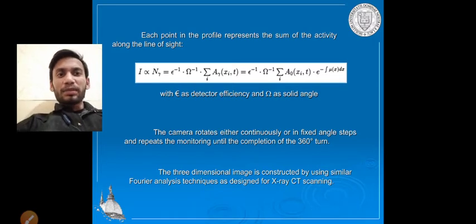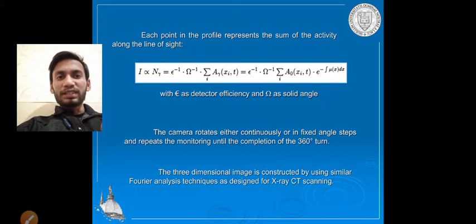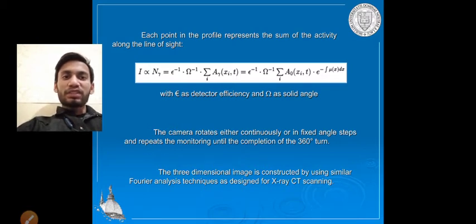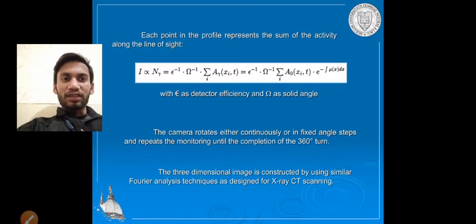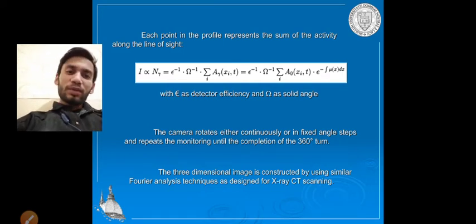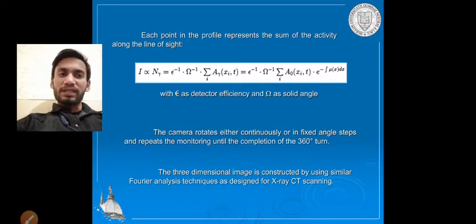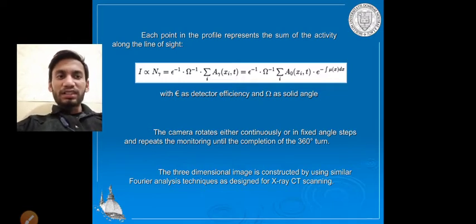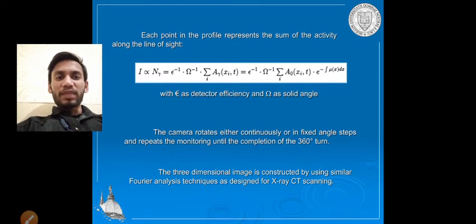Each point in the profile represents the sum of activity along the line. The detector efficiency and solid angle (omega) are represented here. The camera rotates either continuously or in fixed angle steps — for example, moving 10 degrees in 10 seconds — repeating until completion of a 360-degree turn. The three-dimensional image is constructed using a Fourier analysis technique similar to X-ray CT scanning.